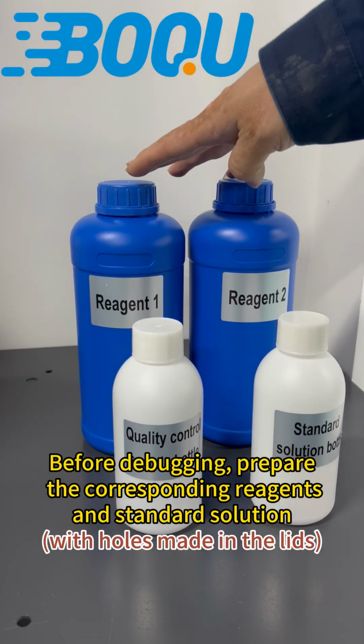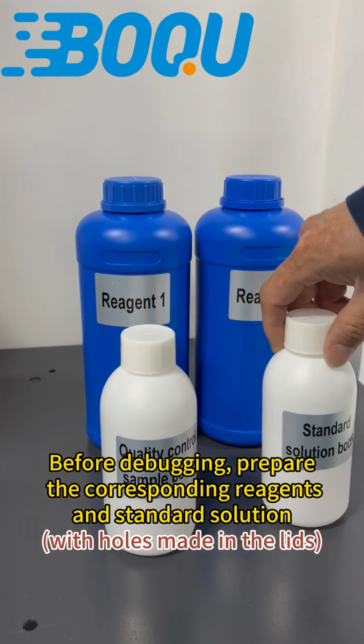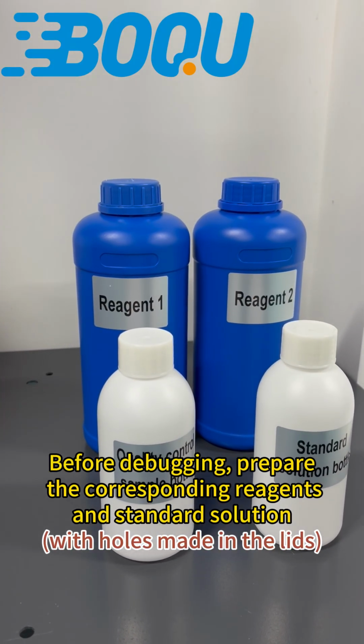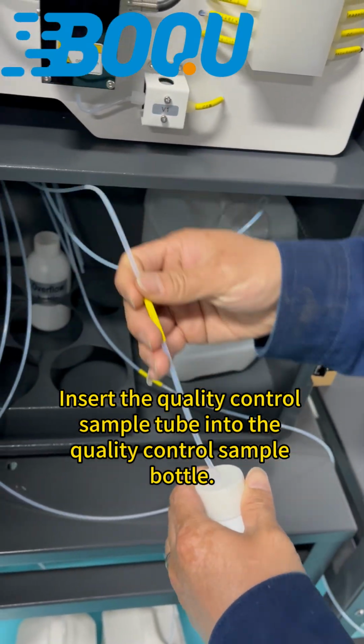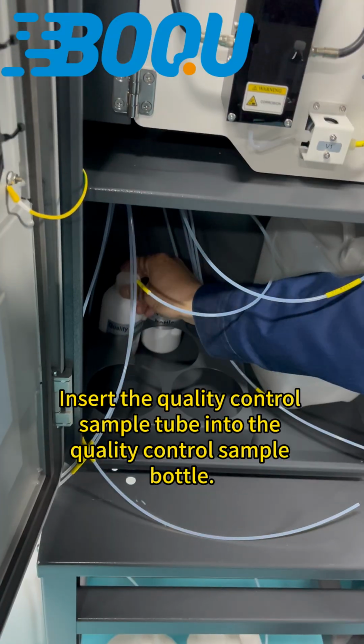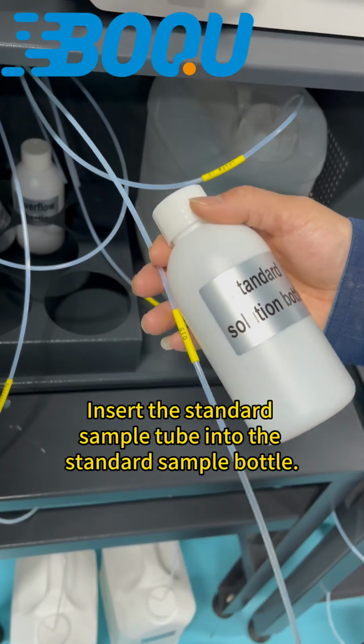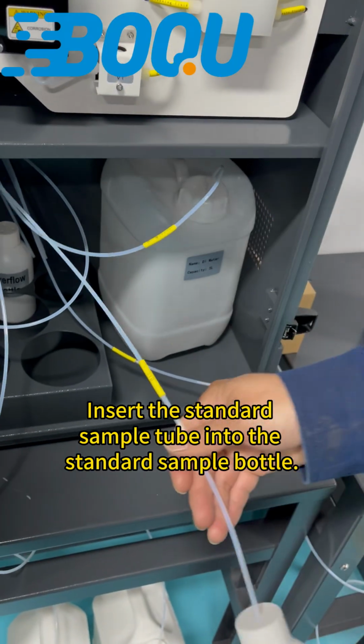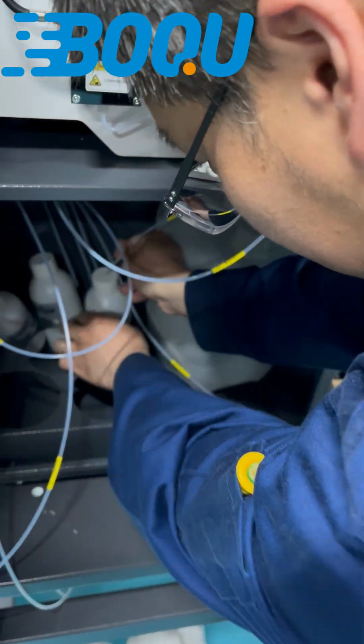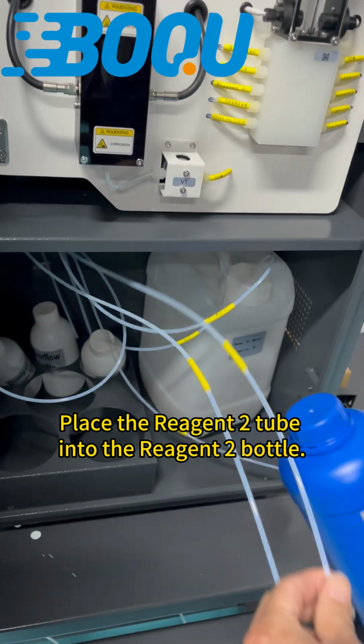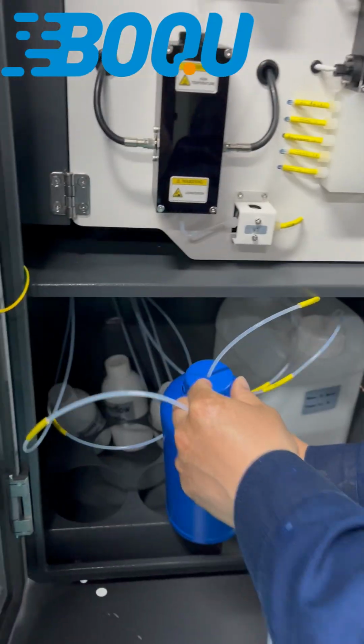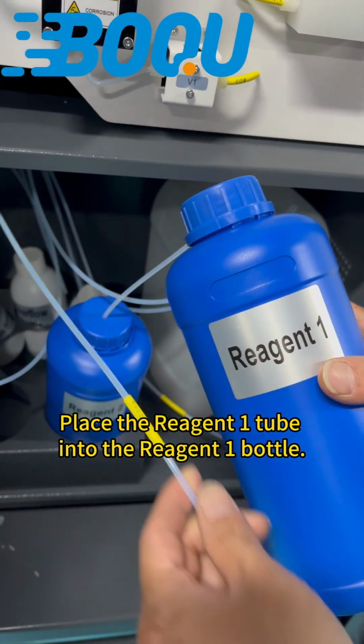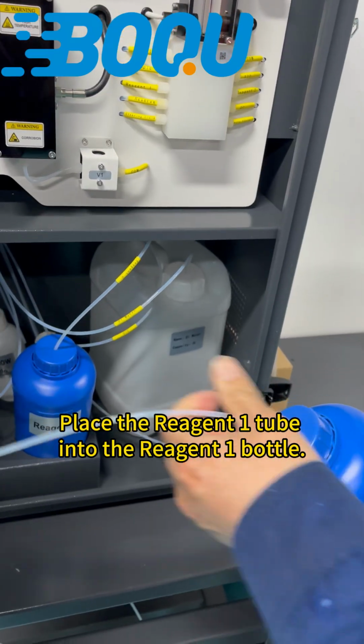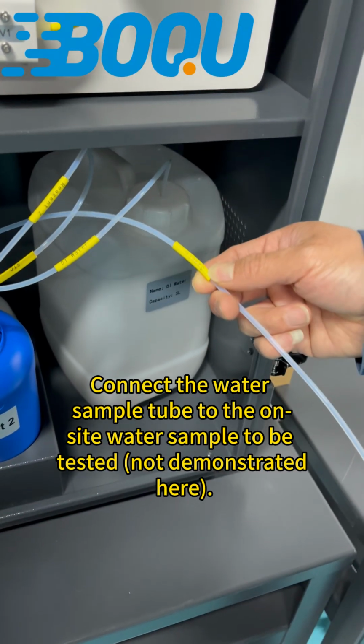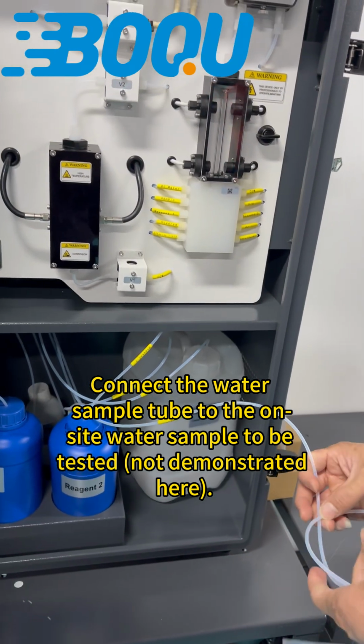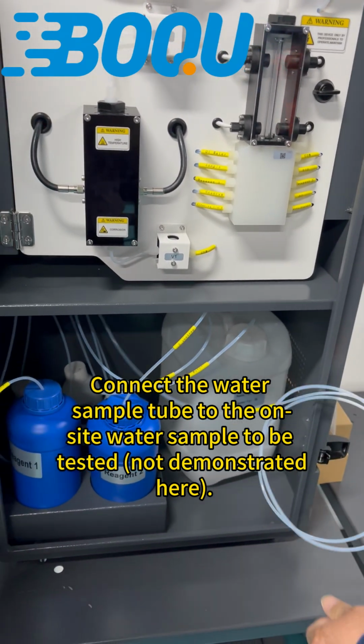Before debugging, prepare the corresponding reagents and standard solution with holes made in the lids. Insert the quality control sample tube into the quality control sample bottle. Insert the standard sample tube into the standard sample bottle. Place the reagent 2 tube into the reagent 2 bottle. Place the reagent 1 tube into the reagent 1 bottle. Connect the water sample tube to the on-site water sample to be tested, not demonstrated here.